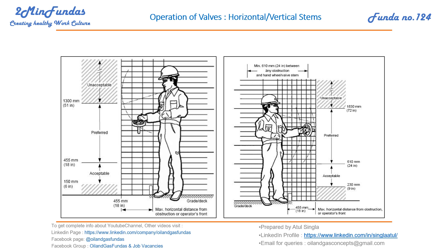If the valve elevation is more than 1300mm, it is not acceptable — it will be very difficult for the operator to operate the valve. Below 455mm, down to 150mm, it is also acceptable, but generally we go for this kind of arrangement in drain valves only. Otherwise, the preferred range is the standard one; this lower range is acceptable only for very small valves and drain connections.